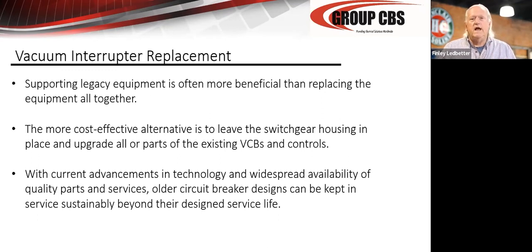As long as you have non-hygroscopic insulating materials and you keep the moisture out, your switchgear will live longer than we will. How you keep the vacuum breaker or the air breaker in service for that 100 years is the problem. With the vacuum breakers, you keep the mechanism in condition, you time it, you test it, you keep it lubed. Every, say, 3,000 operations, you do major maintenance on it. You don't let it sit still for a longer period than about 5 years.